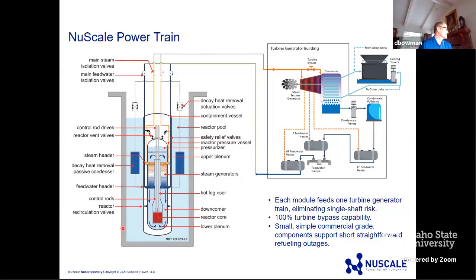You can see the water out here is actually the pool that we talk about. And I'll show a cutaway picture of the building later. And you have this containment volume here. This containment volume is maintained at a high vacuum, and we use that for insulation, much like your thermos would work for coffee. And then inside here is the reactor coolant system, which is maintained at a relatively high temperature. Our average temperature is 545 degrees at power.